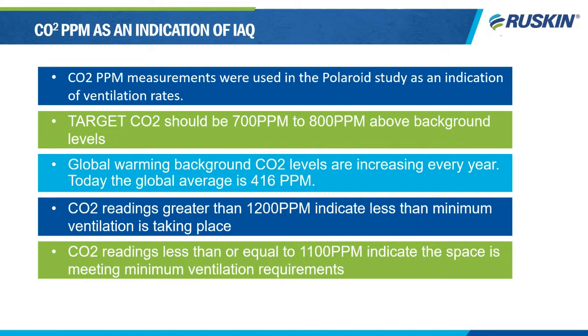So a CO2 sensor reading of 1,200 parts per million or more indicates that the space is underventilated and is not meeting the requirements for the introduction of the minimum amount of outside air required. CO2 sensor measurements equal to 1,000 parts per million or a differential of 700 parts per million or less above background indicates that the correct minimum ventilation rates are taking place or better.